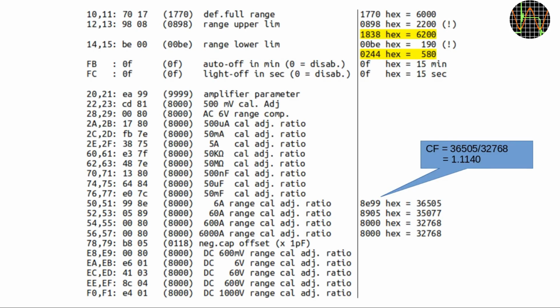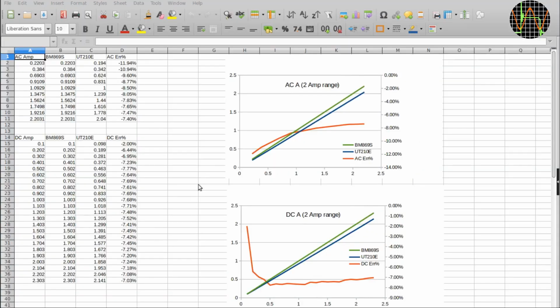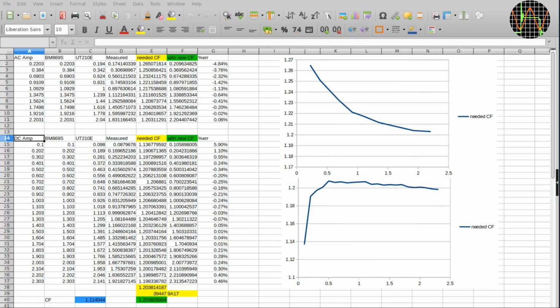If we go briefly back to the content of my EEPROM, we see the cal value of 36,505 for the 6 amp range. This means the correction factor is 36,505 divided by 32,768, or 1.1140. And back to the spreadsheet earlier, we can observe that what we need to fix the problem is indeed a rotation of the blue trace to match the green one. So let's explore this a bit further. We know the current correction factor of 1.1140 from the EEPROM is obviously not right. I put it down here in blue.